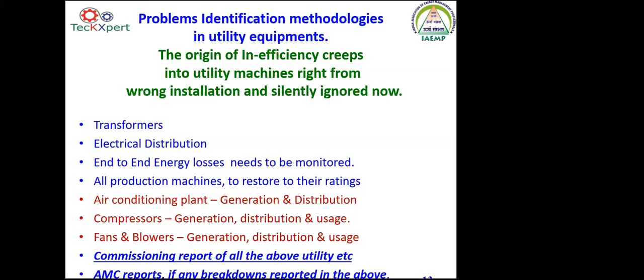These are the areas to be attended to, especially the air conditioning plants in all building segments and building types, all these facility management industries. The generation is at 0.7 kilowatt per ton, as we all talk about. At the point of distribution and at the point of usage, so much dropping and so much loss is happening. It is not only in air conditioning; it is in the compressors, the fans and blowers. Especially in compressors, it is not only generation, distribution, and usage; leakage also happens. Leakage is a variable quantity which is not in control. It has to be controlled, thanks to the latest sonic imagers and other acoustic, ultrasonic measurement devices. We are able to spot the leakages and attend to them immediately.